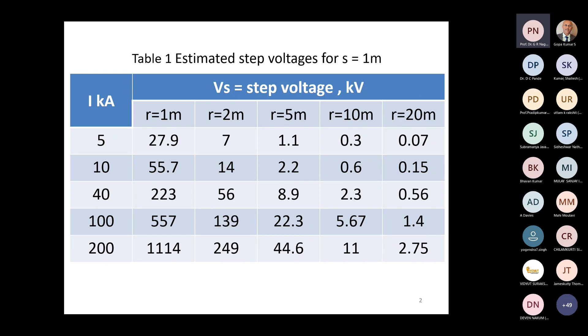Now we have also estimated in the webinar what the likely body currents are if we assume that the body resistance is zero. Body resistance can be negligible in wet weather, for example. Only soil resistance determines the current that flows through the human body. Again, it can vary from distance to distance. If you again consider the same current levels of 5 kA to 200 kA with 40 kA as the mean probability current, at distances of 1 meter to 20 meters, we have calculated the likely body currents, which can range from 150 amperes to 6,000 amperes for a distance of 1 meter.